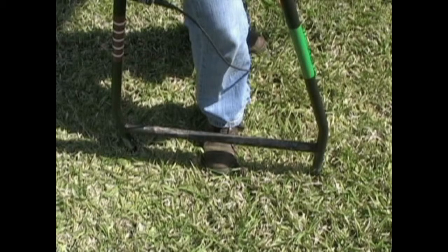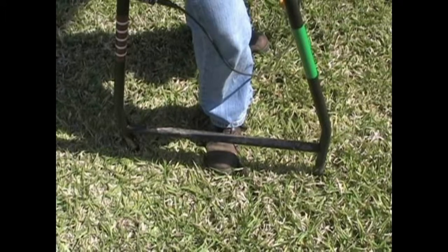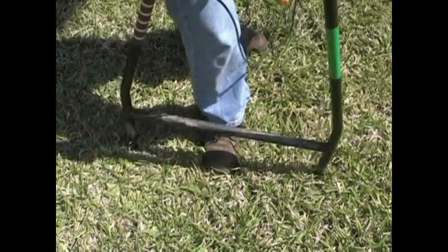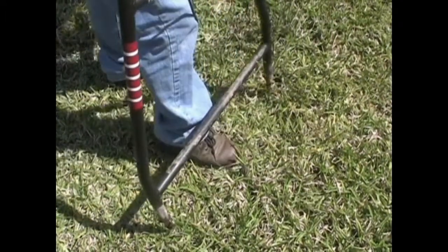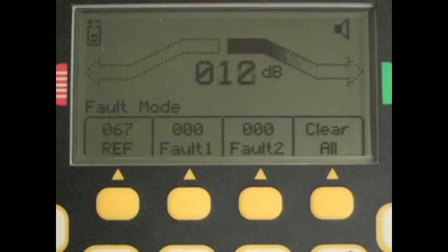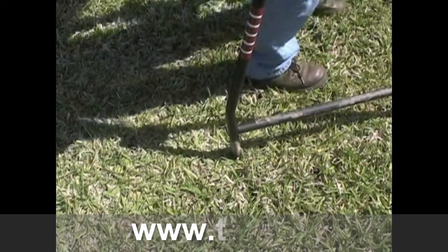Place your toe on the ground at the center point between the two legs of the A-frame. Turn the A-frame 90 degrees one more time to verify the forward and backward location of the fault. When the arrows on the receiver screen balance, the fault is under the center of the A-frame. Verify the fault location by placing the red banded spike into the pinpointed fault location.